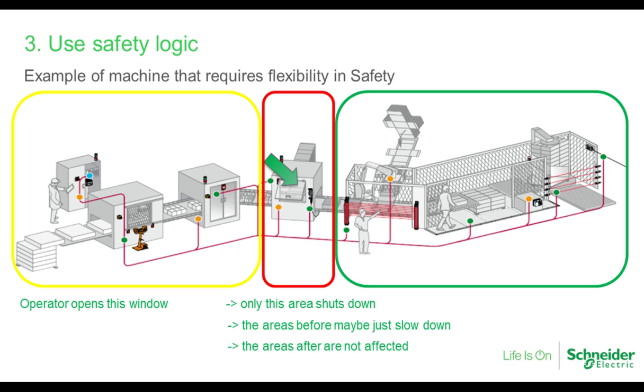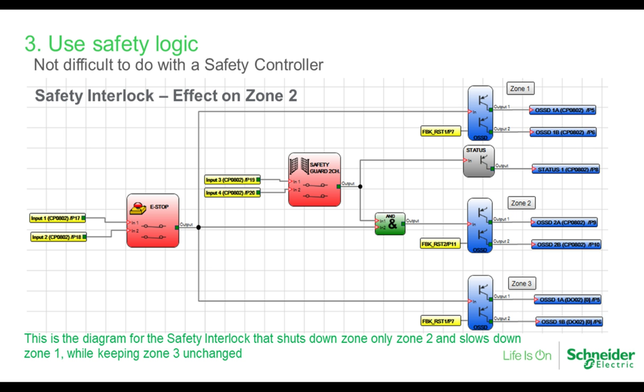And if you're using something programmable like I'm showing here, then if you come up with a scenario where the reaction is different when somebody opens up the door, this is how different the logic is. It's really not that different at all. It takes like 10 minutes to do the programming. And of course, you're going to spend more time in testing and validation and make sure that the sequence of operation is good. But this is really easy.